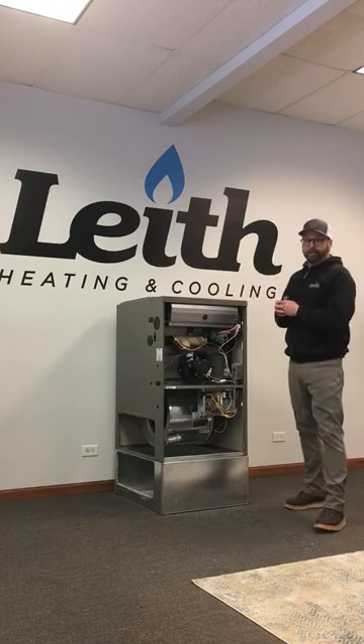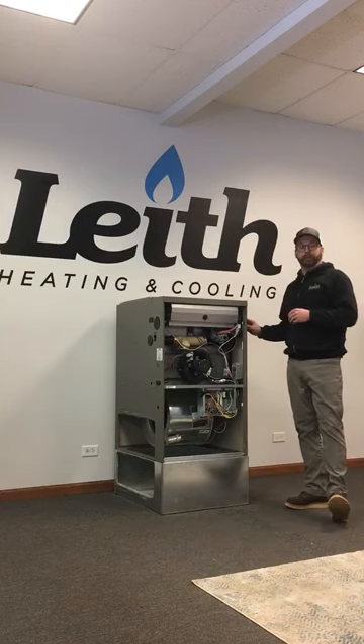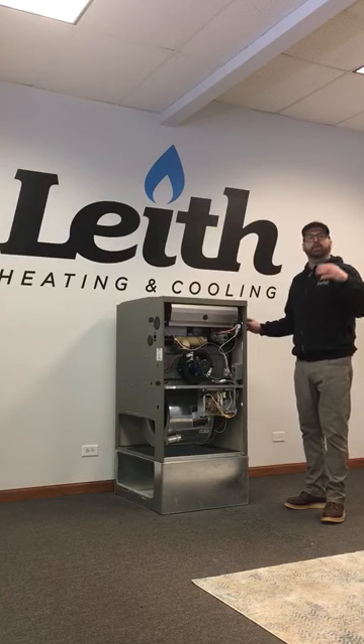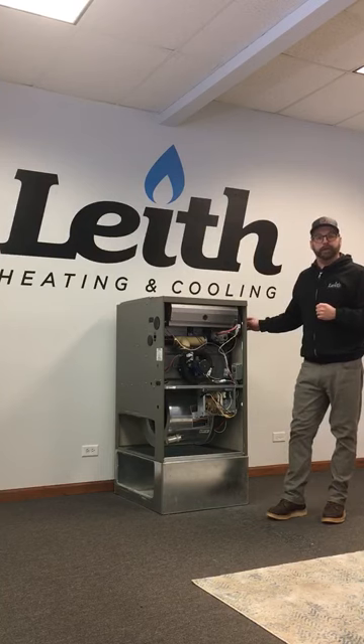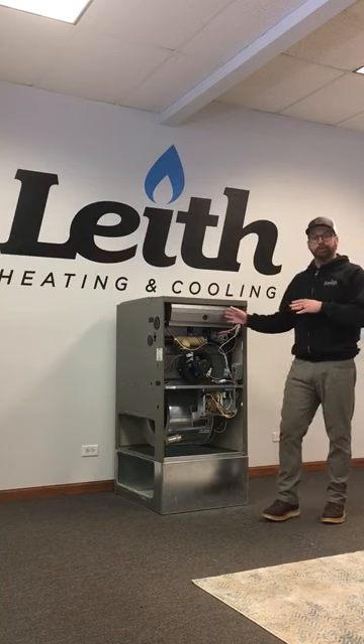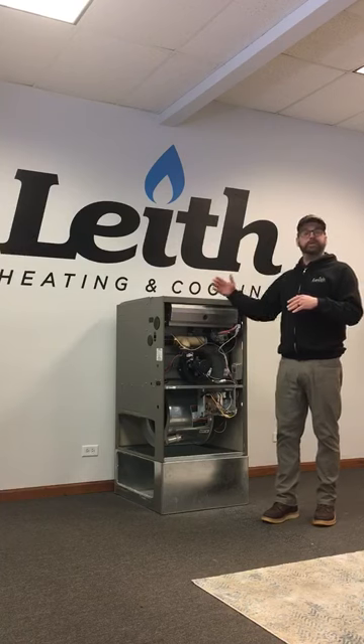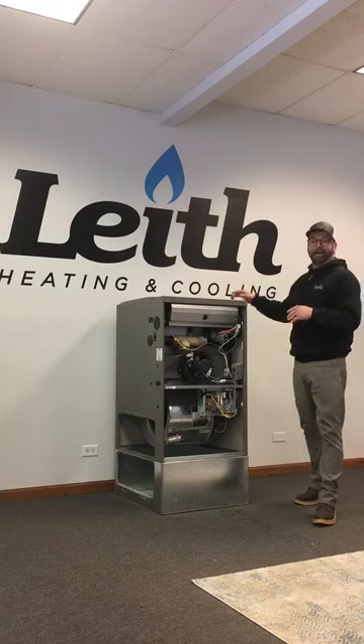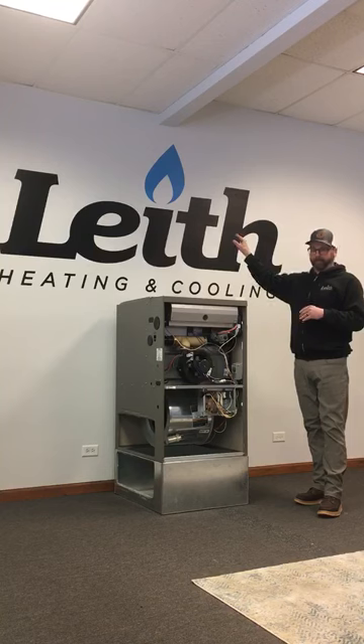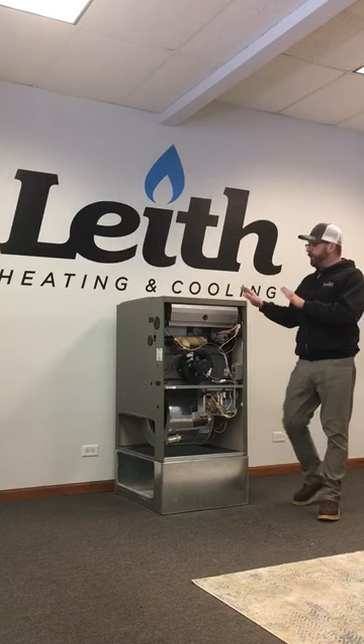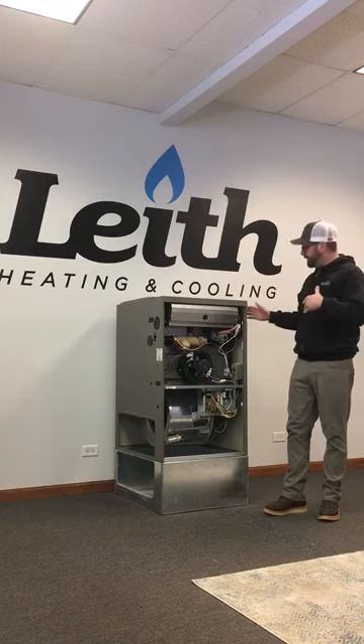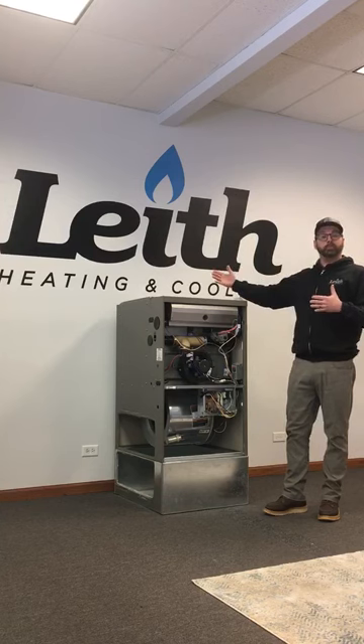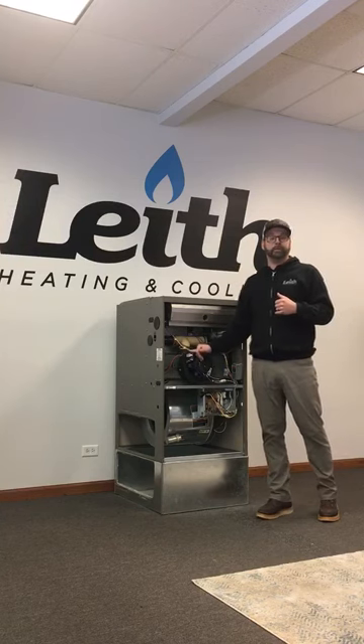It does it on this particular furnace. There's an intake pipe over here on the side that you can't see right now, but I will show a little bit later in another video. It will draw air in through the combustion chamber, through the different heat exchangers, and then back out the exhaust pipe to the outside. It knows that all of these are safe for operation, being that nothing is plugged up or blocked, by the use of a pressure switch.